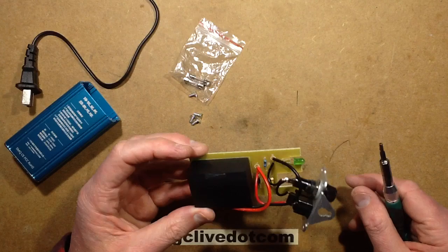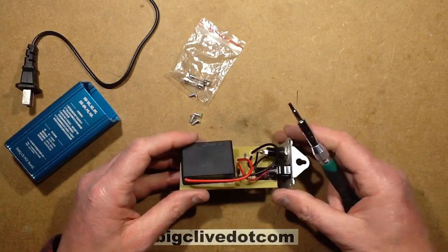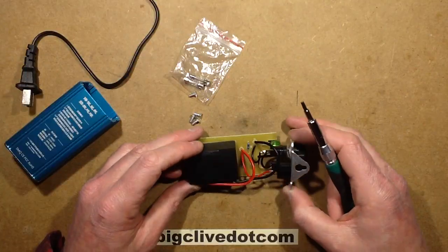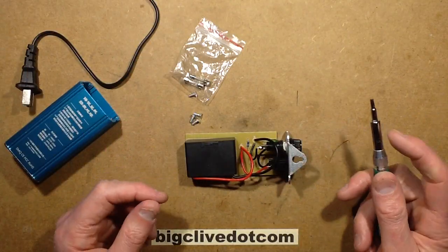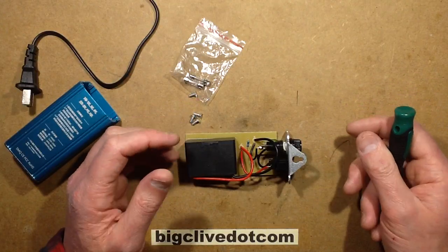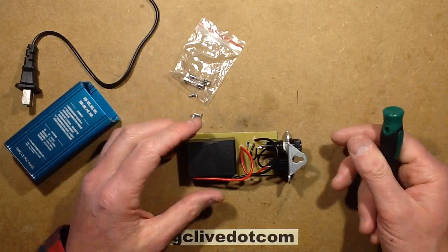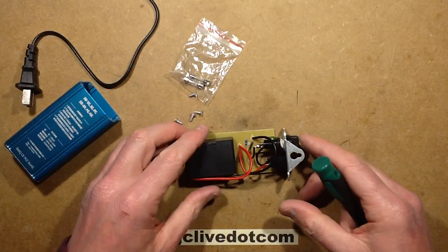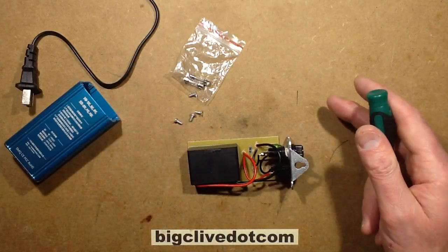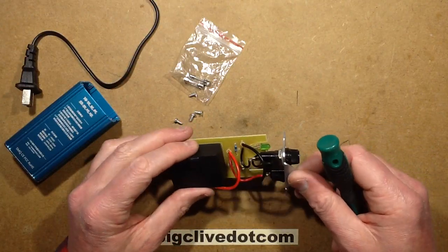So it can be quite useful in large installations, in offices and stuff like that. However, this is just a stab in the dark, throwing a random value capacitor and not knowing what sort of loads are in the house. I've seen the presentations of these where they basically have like the worst load possible, a big lossy motor with no load in it so it's acting like a choke or inductor. And they show it with a power meter, and then they show it with a capacitor, and it's a miraculous improvement. Makes it look like the current's gone down. And it's just basically quackery again, just being charlatans.